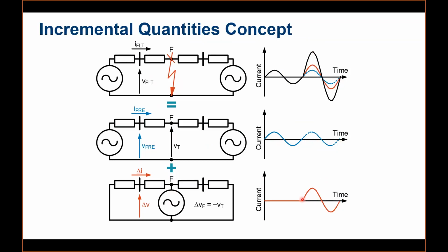We call these delta quantities, or incremental quantities. The changes that happened due to the fault are delta V and delta I, and the others are the pre-fault quantities. All of our discussion in the coming slides will be on the changed quantities. We will not look at what the relay has measured or the pre-fault quantities. Whatever is a change, we can use those values to get elements that are much faster and much more reliable. It also has two elements: one is the directional, and the next is the distance, which we will discuss in the coming slide.